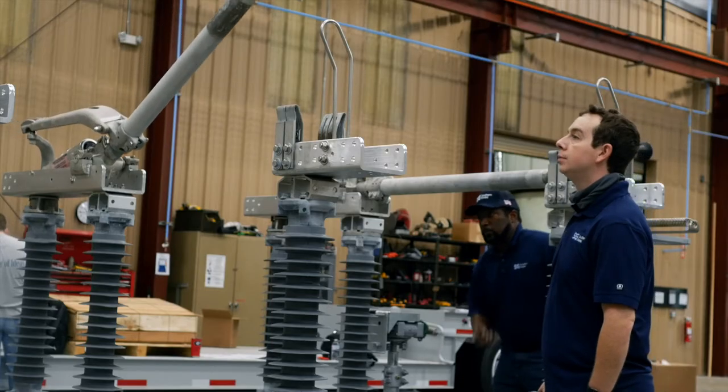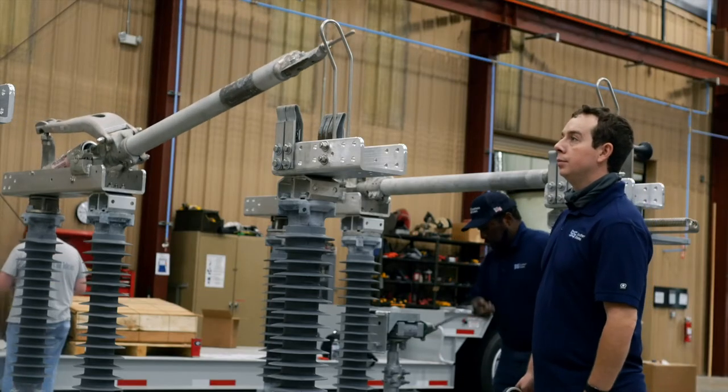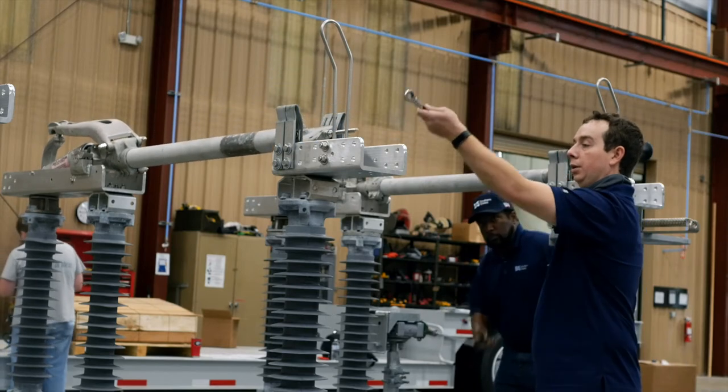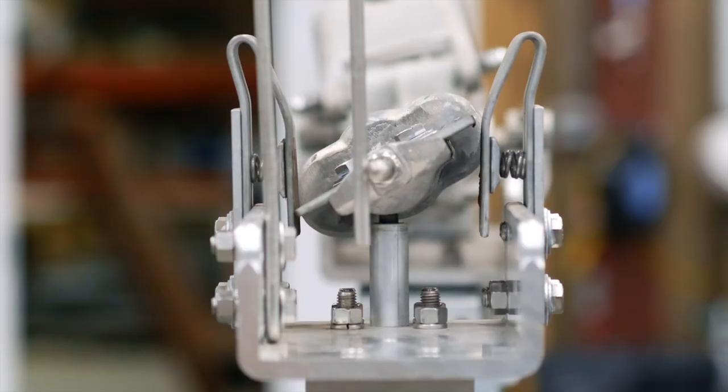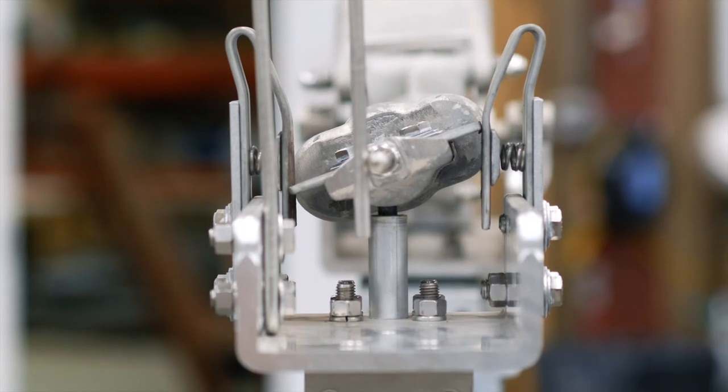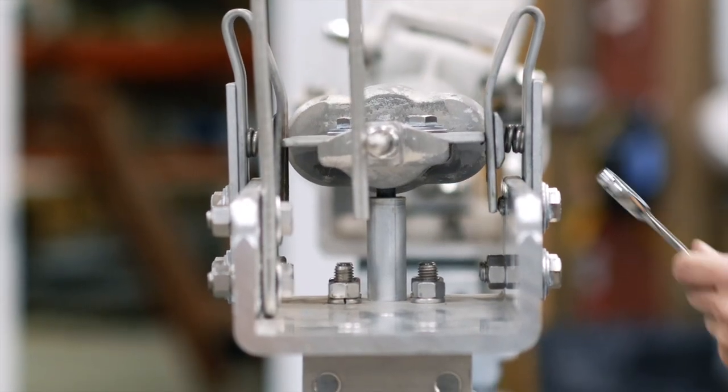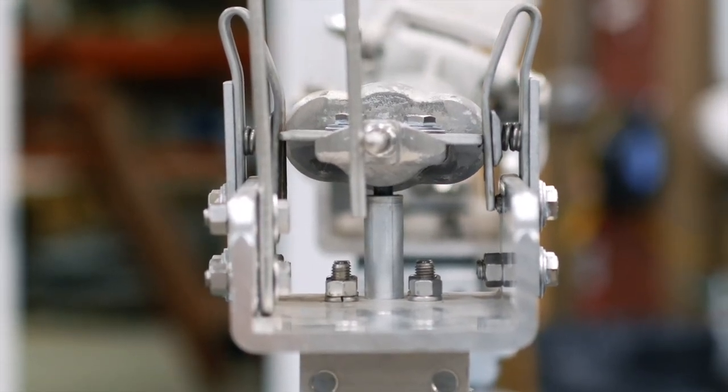At this point, ensure that the switch is in the fully closed position. This can be done by checking that the stop bolt is flush with the insulator and that the switchblade is resting on the stop, toggled and centered in the contacts of the jaw.